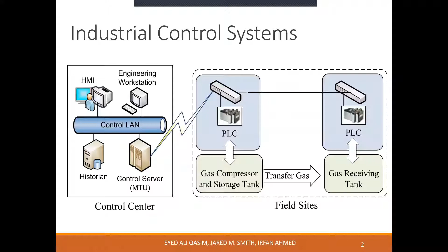The program running on a PLC is called the control logic, and you can write the control logic on the software provided by the PLC vendors called the engineering software. The engineering software often supports one or more high-level programming languages from the set of 5 languages mentioned in the international standard. The control logic is written and executed in the form of rungs, where each rung contains different types of instructions. As you can see, the two figures show the timer program written in instruction list and the ladder logic. In ladder logic, one horizontal block represents one rung, and different instructions present in it are executed from left to right. Similarly, one block of code in instruction list represents a rung, and the instructions are executed in a vertical order.